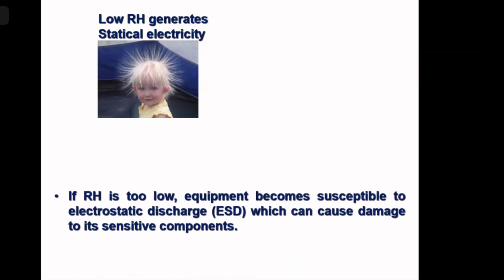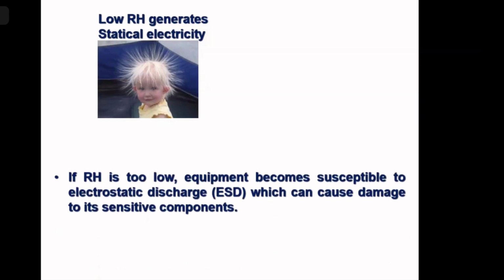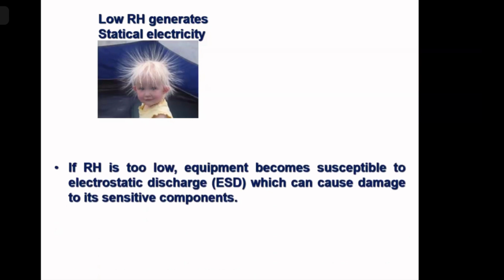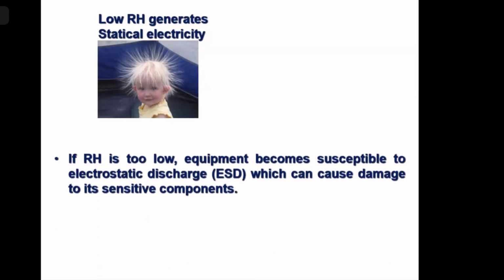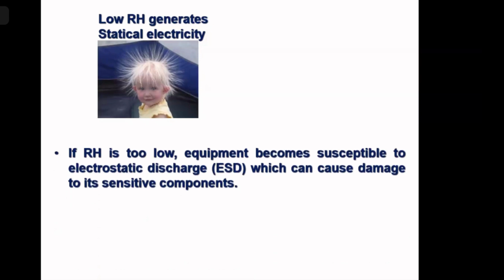And when the RH is high, say 80% RH inside the electrical room, that may at times create condensation of water on the cold surfaces. And that condensed water may again cause short circuit between two closely spaced conductors or electrical elements of an IC or a PCB. So, electrical rooms also should have controlled relative humidity. Next. If RH is low, it produces electric discharge, static electricity discharge. Next. RH is high, water condensation. Next.